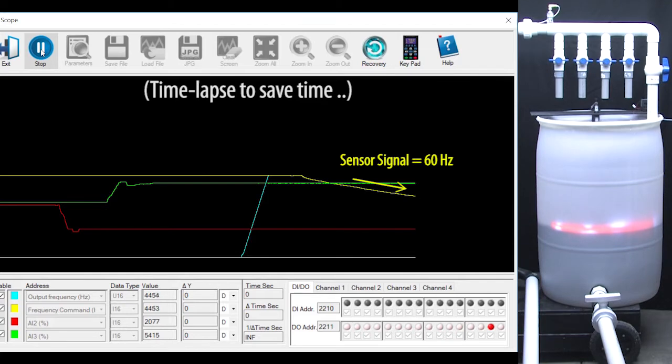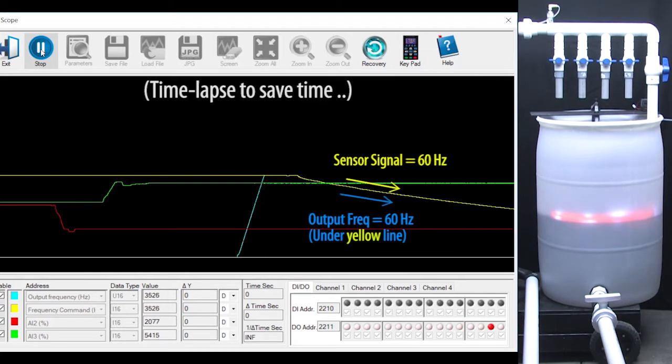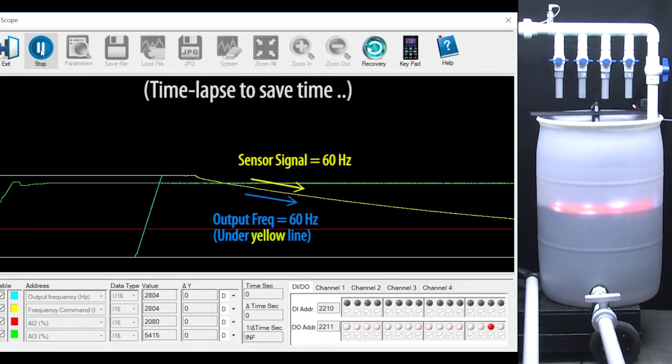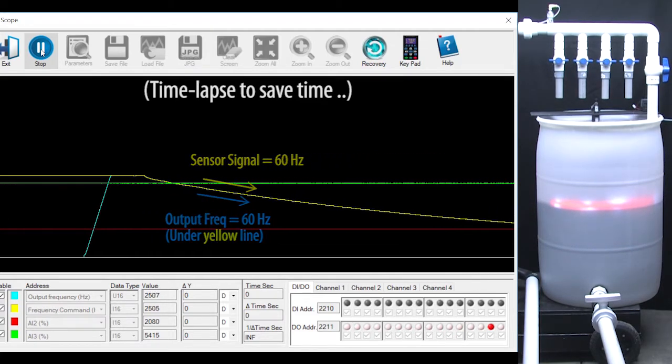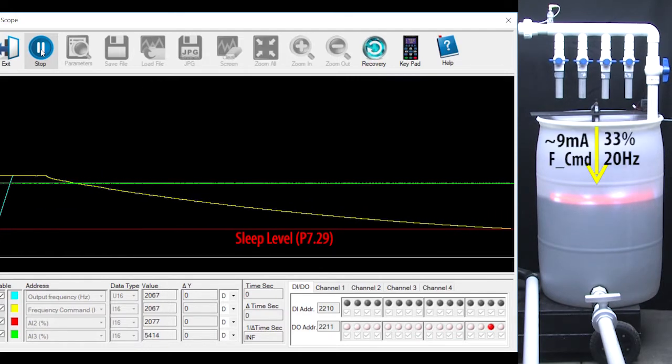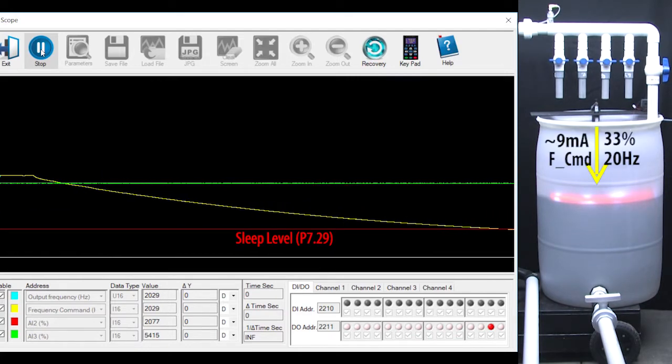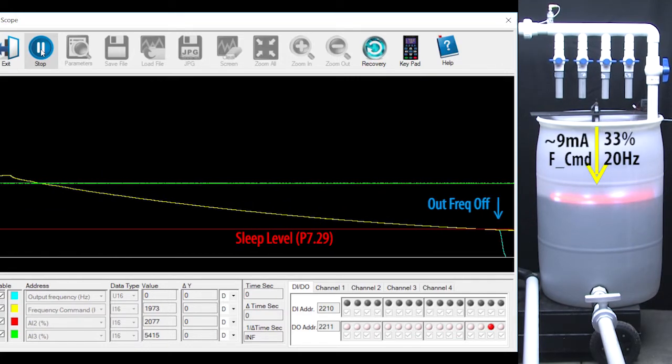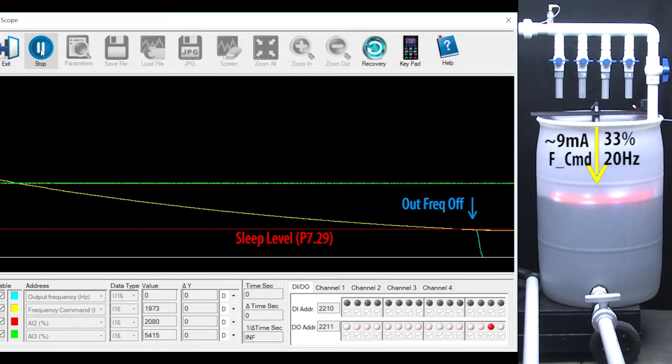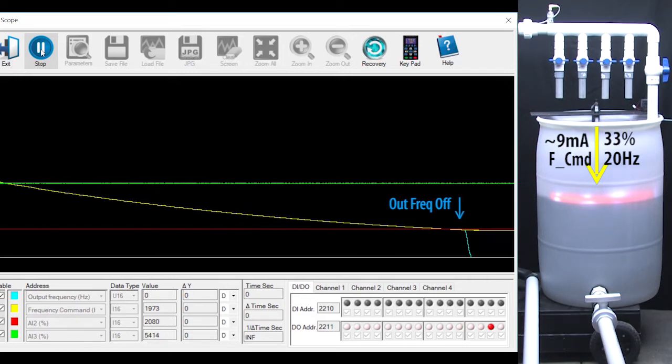As the water level rises, the sensor signal gets smaller and smaller and the motor runs slower and slower. Eventually it gets to the sleep level we set in parameter 729 and sleep mode disconnects the frequency command from the output and the motor stops pumping. Perfect.